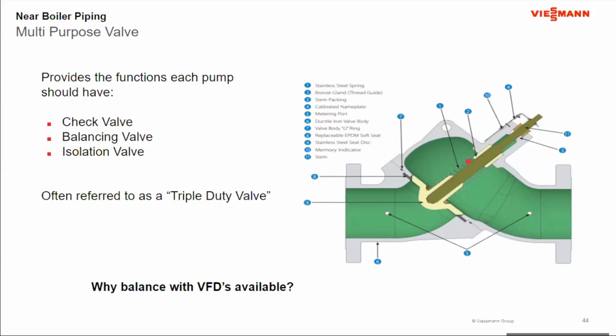Okay, you notice it has a spring along here. This shaft and the seat of the valve are not firmly attached to each other. The seat and the shaft can move independently. So if I back that shaft out, and why am I going to back that shaft out? It's because I'm going to balance the system. So I can use that as a balancing function. I back that shaft out. I have my indicator here, and then I also have my memory indicator in case I use it for isolation. And then I have a pair of ports here that I can put PT plugs in.